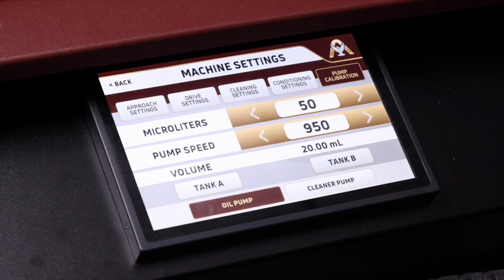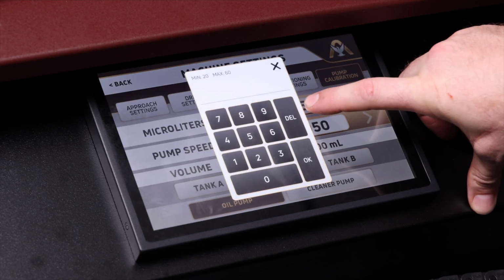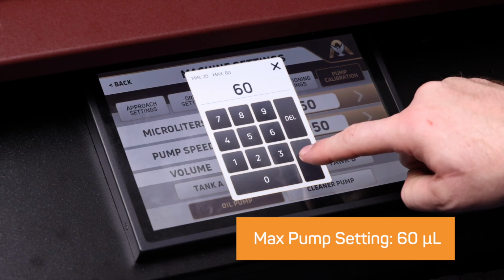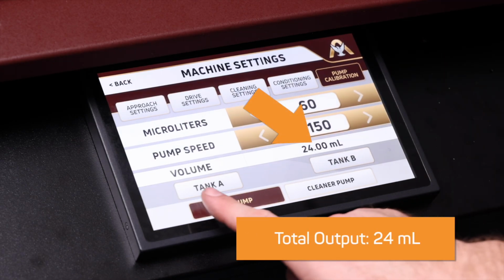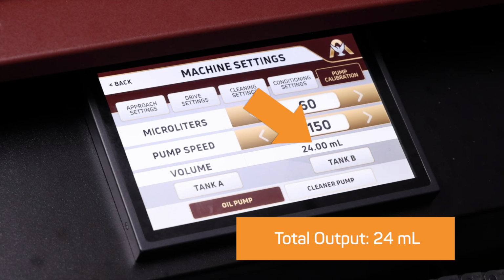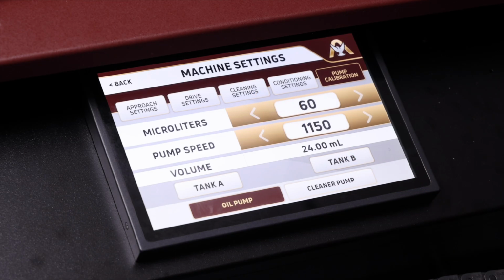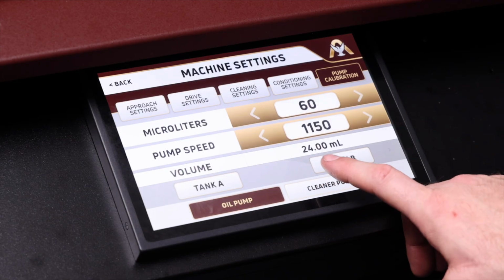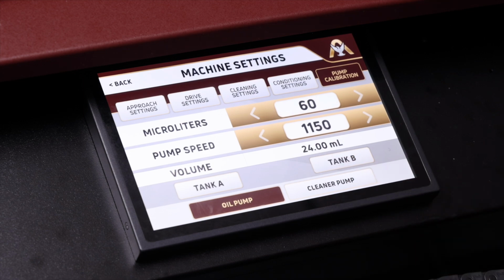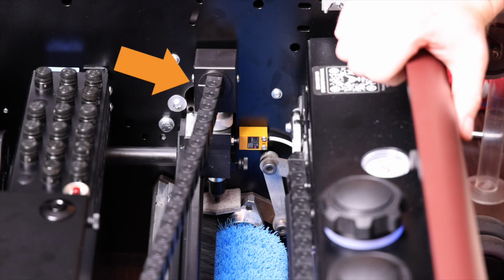To calibrate your oil pump, we will want to go to the max setting of the pump. 60 microliters is the max setting for a total output of 24 milliliters per tank. You will run the test, and if you get a value above or below 24 milliliters, an adjustment will be necessary. 60 microliters is the only microliter setting that we will manually adjust the pumps from. To remove the tip from the oil head block, we will loosen the thumb screw at the bottom of the block.